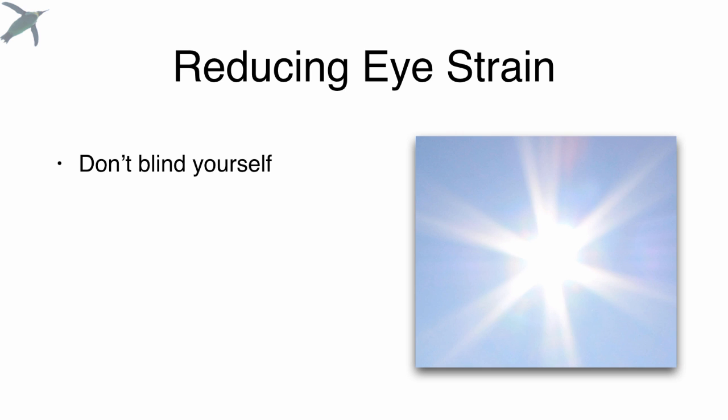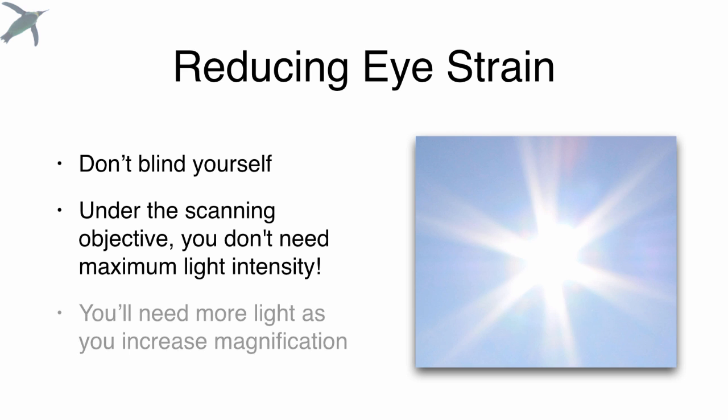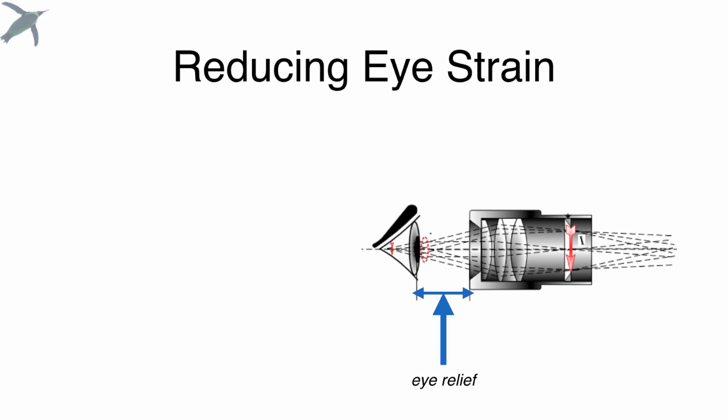Last thing I want to talk about is how to save your eyes while spending all this time looking in the microscope. Number one, don't blind yourself. I find my students tend to use way too much light. Especially under the scanning and low-power lenses, you don't need that much light. As you increase magnification, that's when you need to increase the amount of light coming through. So make sure you adjust that and you're not always looking under maximum illumination.